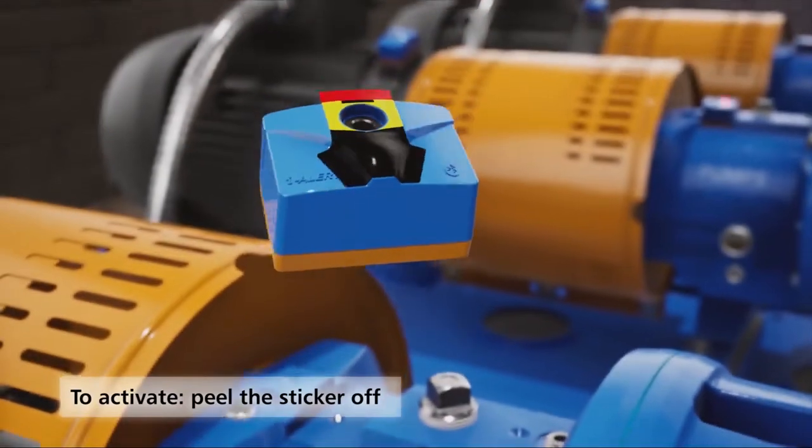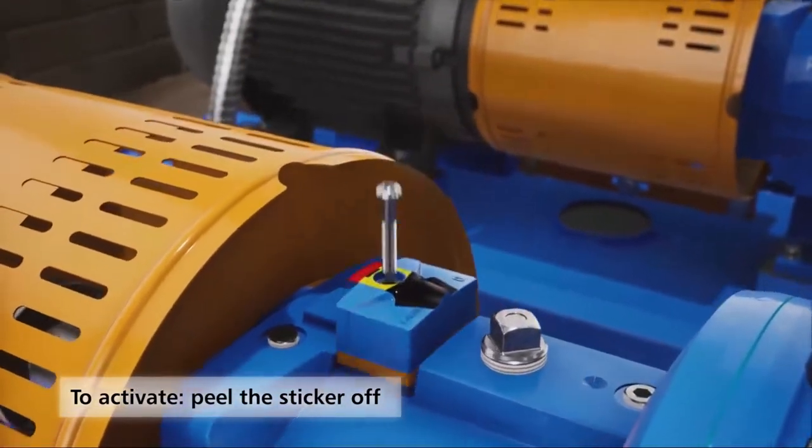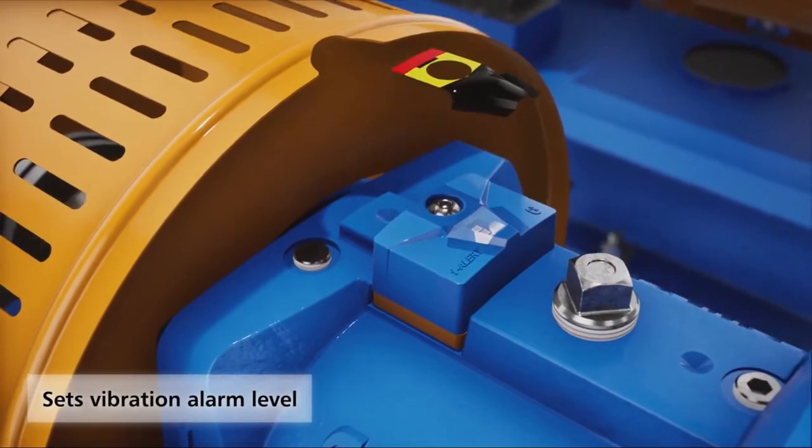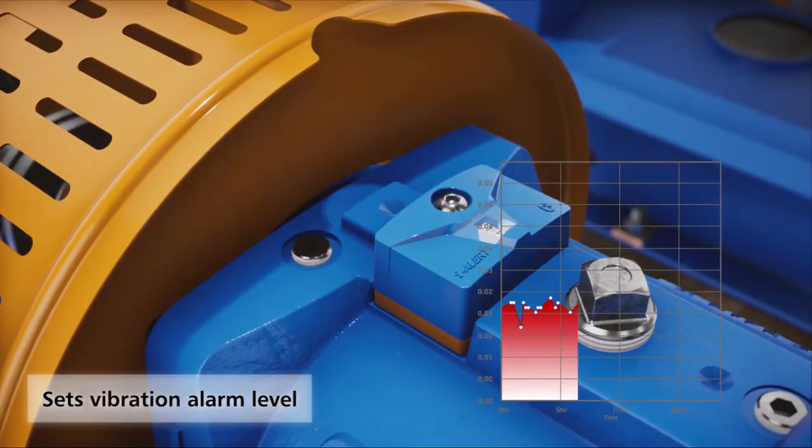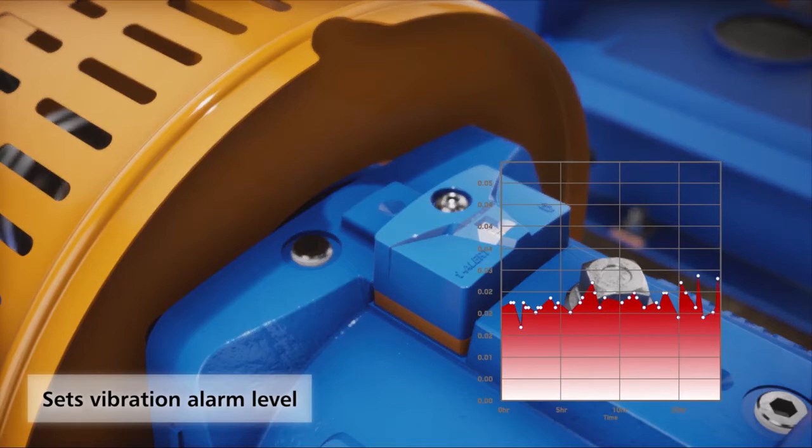When activated, the iAlert 2 takes baseline vibration readings for 25 equipment run hours. This baseline is used to set high vibration alarm levels. No programming is required by the installer.